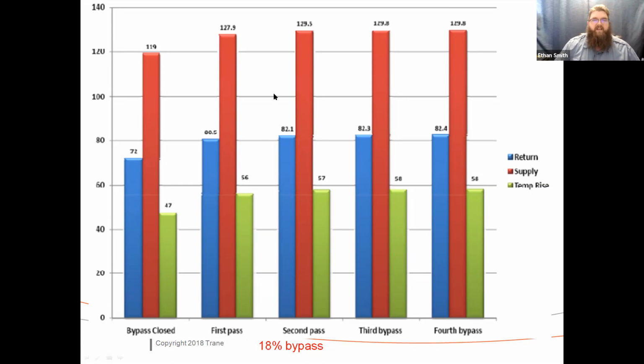That 18% bypass, you can see what happens to my temperature split, guys. I get up around 58 degrees, which is going to be right up against the upper limit for a temperature rise across most furnaces. Okay, I've gone from 119-degree discharge temperature to 129. You can see that my return air temperature is also getting up towards the upper limit on what my furnace will tolerate as well. Most furnaces are only going to tolerate up to an 85-degree return. Okay. So we start to see that.